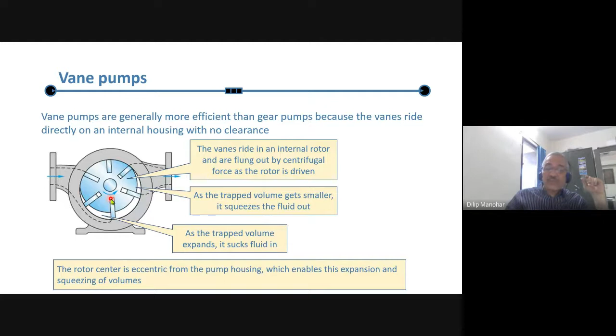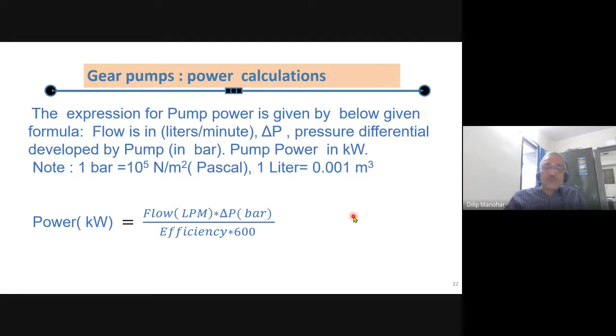Now we come to some power calculation. Gear pump has this expression. Now we'll use this formula for gear pump power calculation. Power is nothing but flow times pressure drop divided by efficiency times some constant. So what is the formula? Flow should be in liters per minute. Pressure drop delta P or differential pressure should be in bars. And one bar, you must have noted, is 10 to the power 5 Newton per meter square, pascals, and 1 liter is 0.001 meter cube. So this is the formula for power calculation.